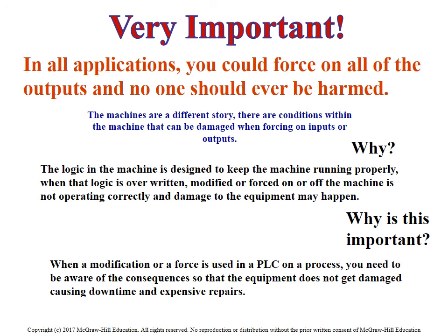The aspect that I want to make sure everyone's clear on, though, is that even if you turn on a force, at no point should you ever have to worry about hurting an operator or somebody working on the equipment. It should never be a case of safety. Safety is controlled outside the PLC, always. So keep that in mind.